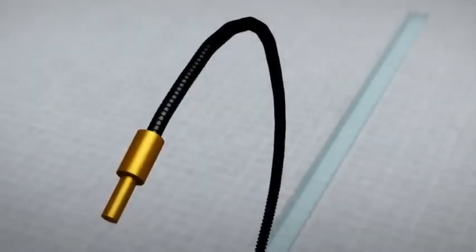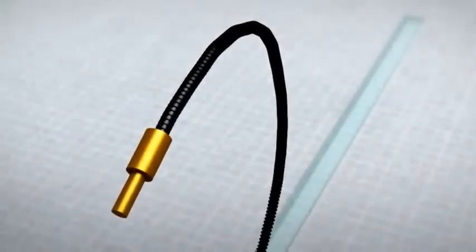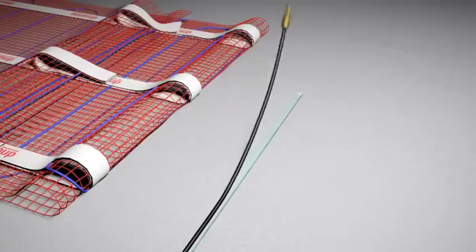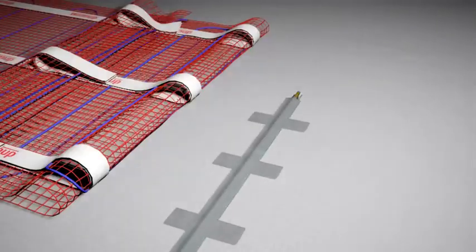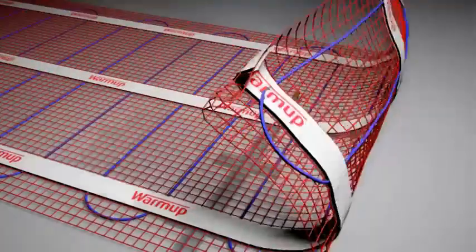The floor probe measures the actual temperature of the floor, allowing complete, accurate control of the system. If the probe or the power cable sit proud of the subfloor, you may wish to chisel out short channels in the subfloor. Tape down the floor sensor at least 300mm into the heated area. Position the floor probe evenly between two of the heating elements, making sure not to cross the heating wire.